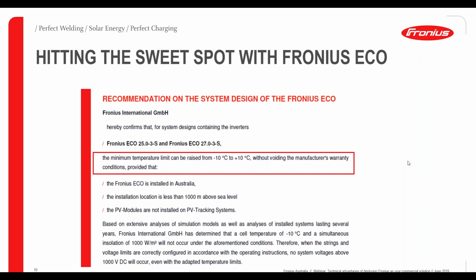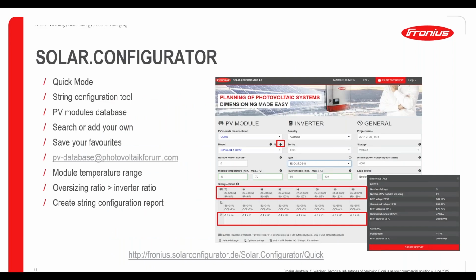So there is a recommendation specifically from us that as long as the system is installed in Australia, it's less than 1,000 metres above sea level and the modules aren't on a tracker sort of system, the minimum temperature can be raised from the -10 that's typically used up to +10 without voiding any of our warranties. So I won't go into specifics today with the solar configurator, and by all means you can get in touch with us if you'd like more information on how the configurator works.